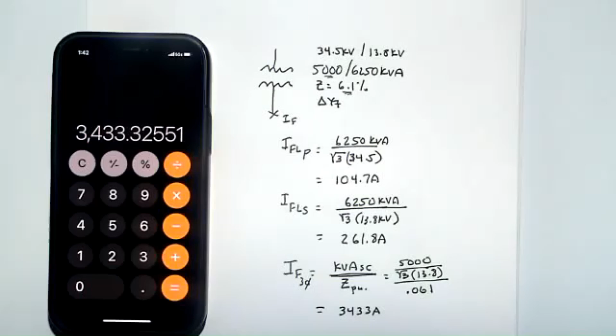6250 is the most kVA we can get through it. So the most kVA means, in order to use the full capacity, we want to base our primary current on that 6250. If you base it on this one, you're just limiting the capacity of the transformer artificially by putting a breaker or something ahead of it and limiting the capacity of the load. And then for the fault current, we used 5,000, or we used the base rating in the base impedance.